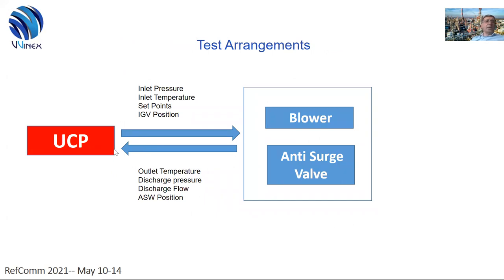The test arrangement was a blower with anti-surge valve. We did not use the discharge piping, as this piping configuration did not have much influence on process dynamic behavior for this particular case study. As input parameters, we used inlet pressure, inlet temperature, set point in regards to output pressure and flow, and IGV positions. Those inputs are supplied to the UCP, and as output parameters we used outlet temperature, discharge pressure, discharge flow, and also anti-surge valve position.